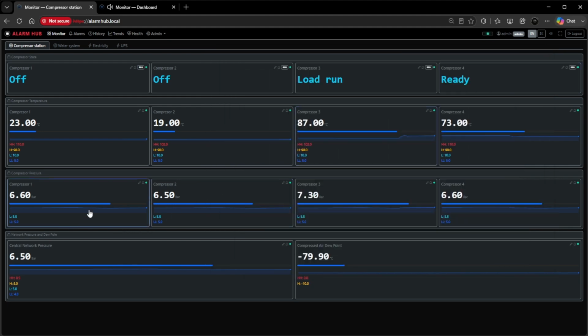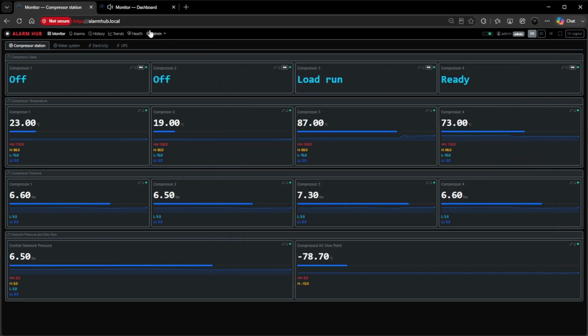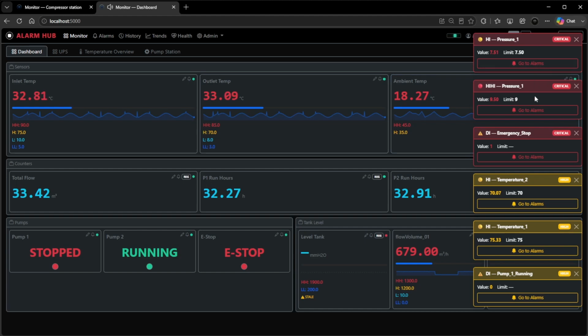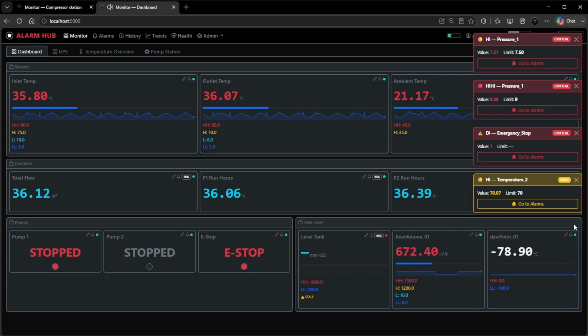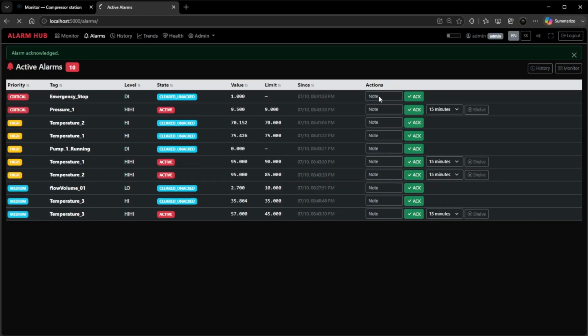When a value crosses a limit, an alarm fires. The engine follows ISA 18.2, the process industry alarm standard. An operator has to acknowledge it, so nothing ever disappears silently. And the alert reaches you two ways: an audible tone right in the browser, and an email straight to the people responsible, so a problem doesn't just sit on a screen that nobody's watching.